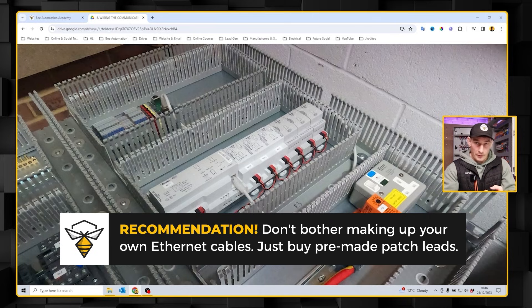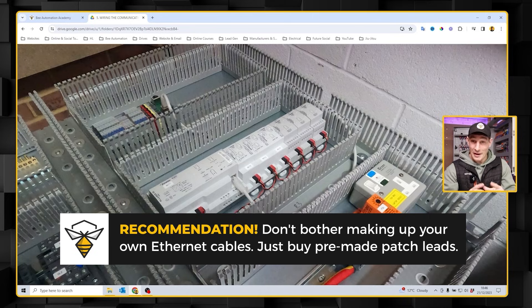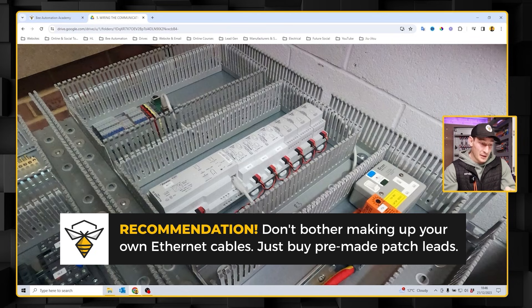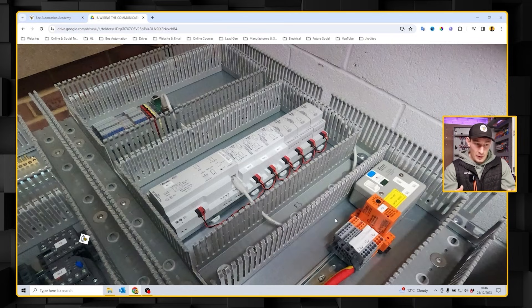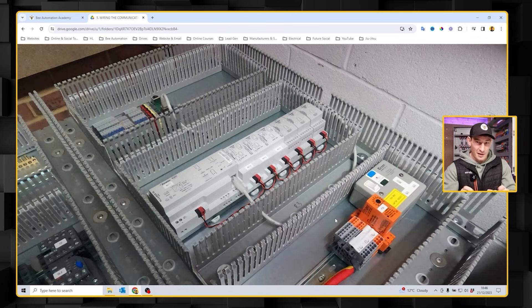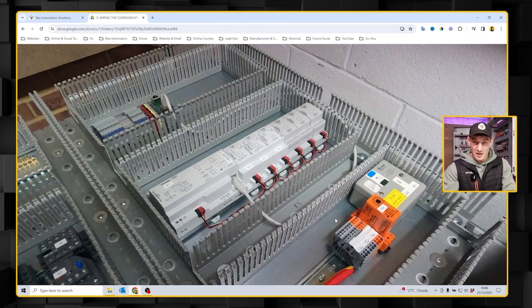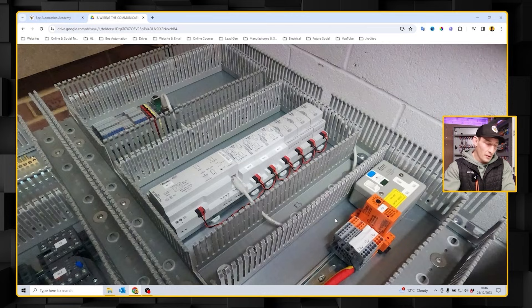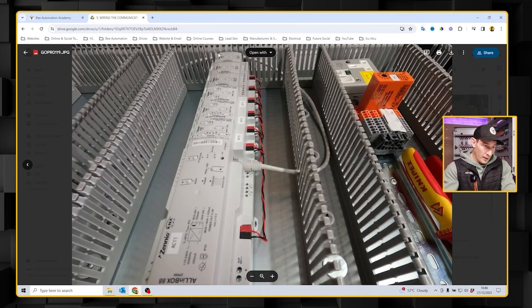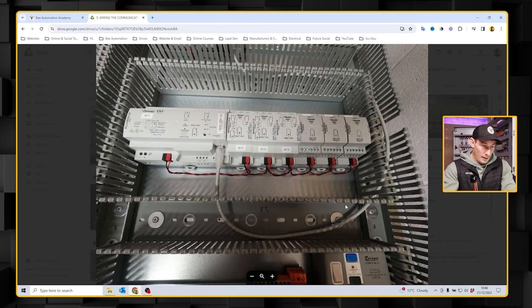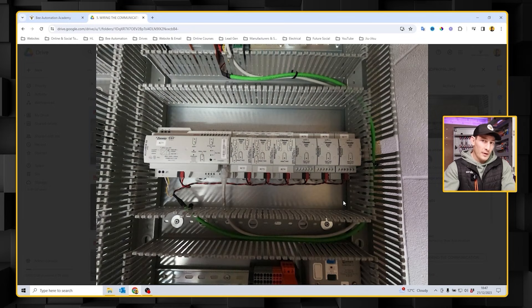This is what it looks like completed with all of those little links cut to the right length for the KNX bus, and also you'll notice that I've just added in an Ethernet patch lead. My advice would be don't bother making up your own data cables, Ethernet cables, RJ45 cables, whatever you want to call them - just buy patch leads. They're cheap as chips, they're already pre-tested, they have loads of different lengths, so it's just far easier and quicker to buy patch leads.